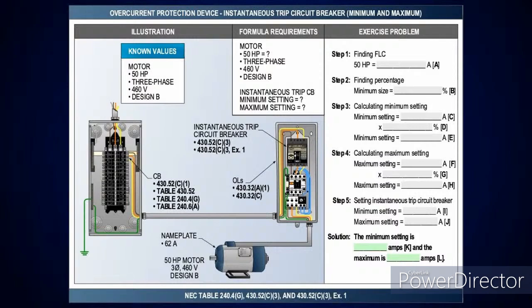If you just go look at what they did in other sections of the code, and you've heard me say this many times, I look at all the code, and I pull out different parts all through the code to see if everything is lining up. And they've done this. Go look at 440.22(A) now, and see if it doesn't look like what it is over in 430.52(C)(1). Then tell me, how did they determine a minimum and maximum on the AC unit?